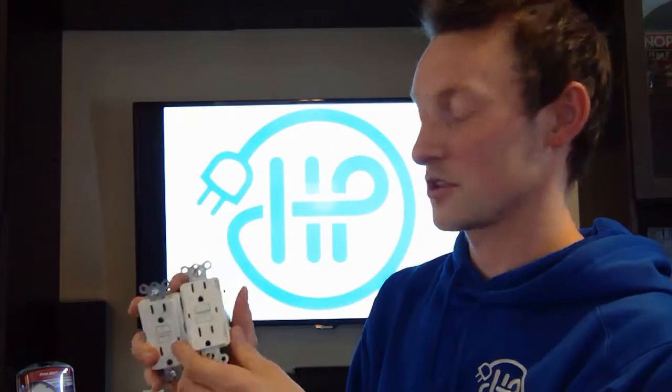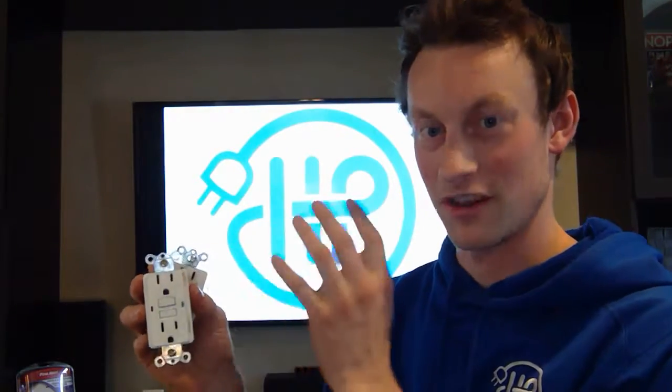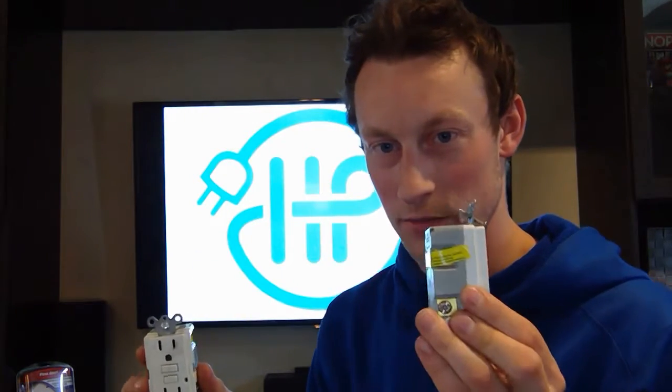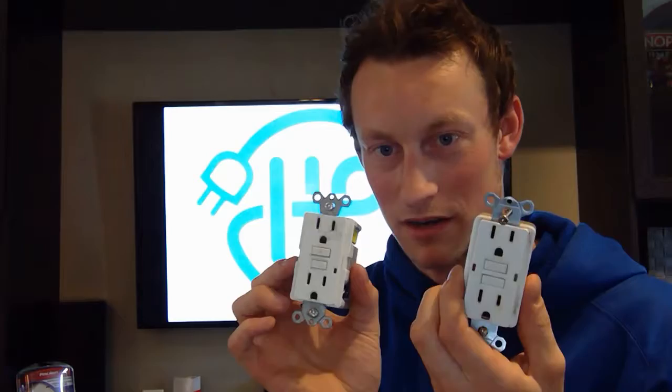Now, if there's power going to the receptacle, you can actually reset it. You can test it. The test will simulate a 5 milliamp or 6 milliamp current, small current to ground. So it will kill the power to the receptacle, but not to your breaker up the line. So when you hit your test button, boom, it's going to send 5 milliamps to ground right at your receptacle. It's got a testing feature inside your receptacle. They're a great unit, a little bigger than your average plug, but they will work.